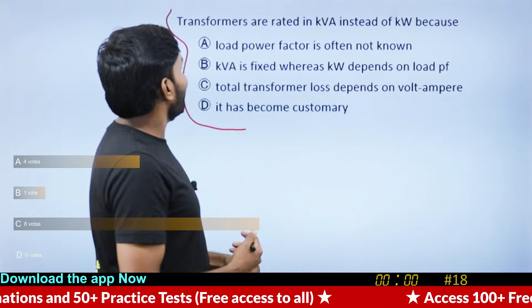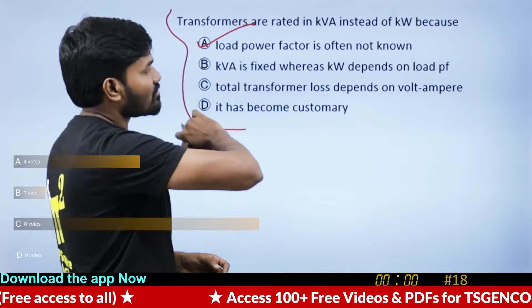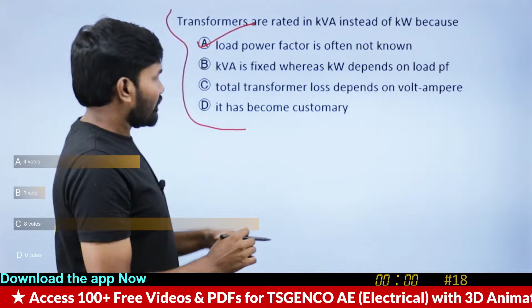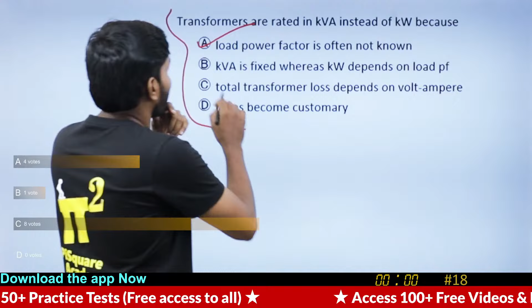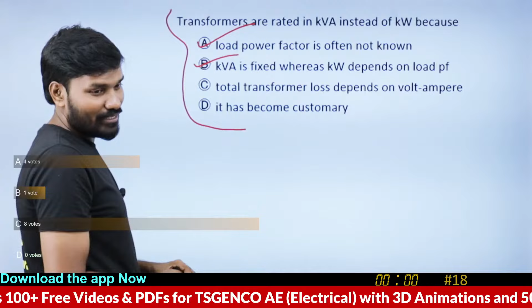So B and C are true: total transformer losses depend on volt-ampere, and load power factor is often not known. But you can't say only this is the answer. The volt-ampere statement is true, no denial there, total transformer loss depends on volt-ampere, that's true, but that's not the reason we included it. We included it because kVA is fixed whereas kW depends on load power factor, and load power factor is often not known, that's also true. So A and B are the right answers rather than B and C.